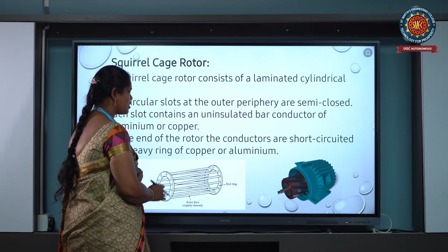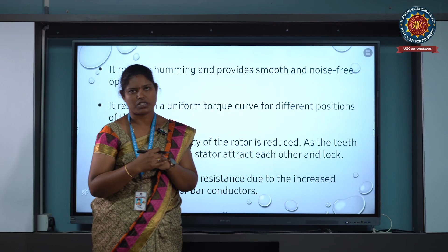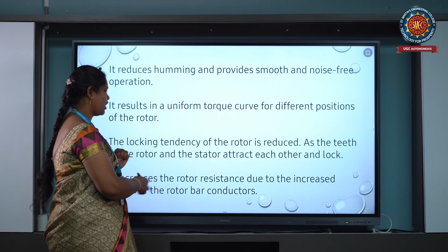The skew position is considered in order to reduce the noise. Also, as the rotor consists of slots in the outer periphery and the stator consists of slots in the inner periphery of the cores, when you place the rotor inside the stator there is a possibility of locking of the rotor inside the stator. So when you place the rotor conductors exactly parallel or perpendicular to the axis, there is a chance of magnetic locking. That magnetic locking can be avoided when you use the skew position. What does this reduce? First, the humming or noise coming out of the rotor, so that smooth and noise-free operation is possible. Second, it can give uniform torque in different positions, and third, magnetic locking can be decreased.